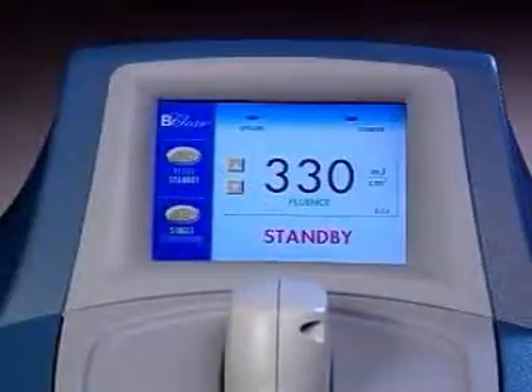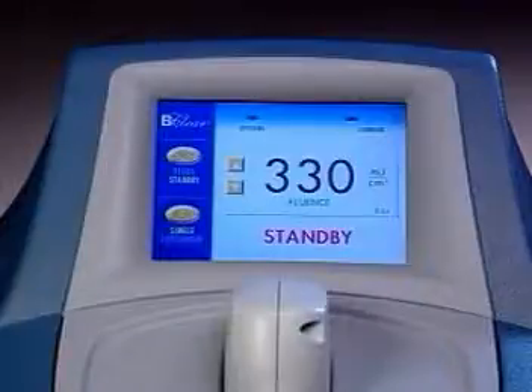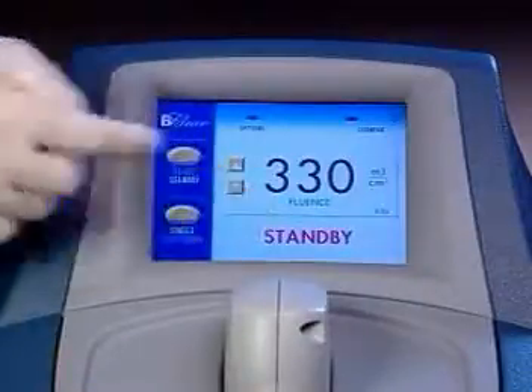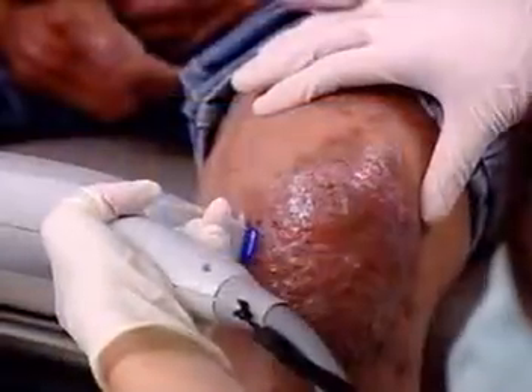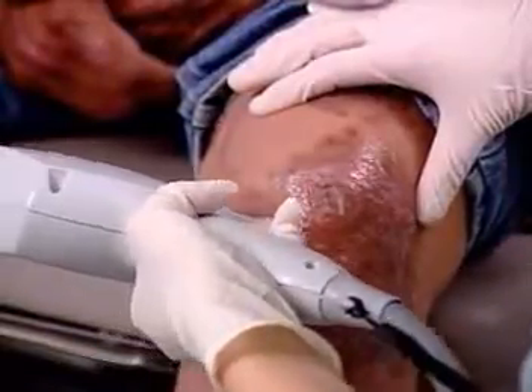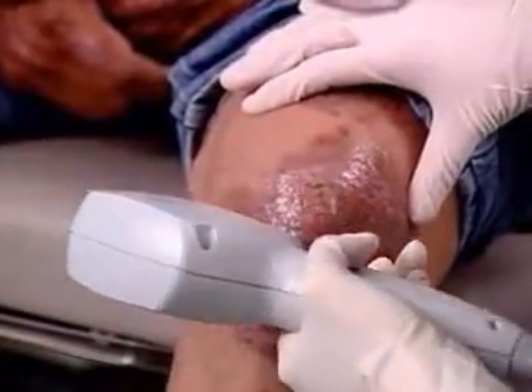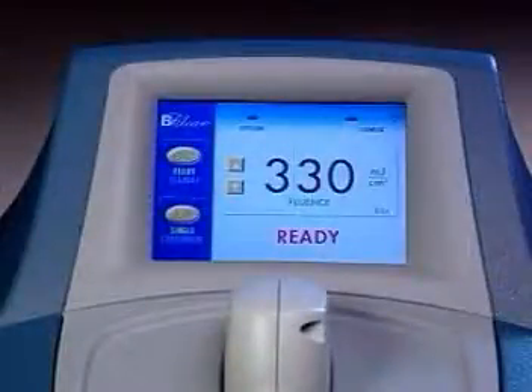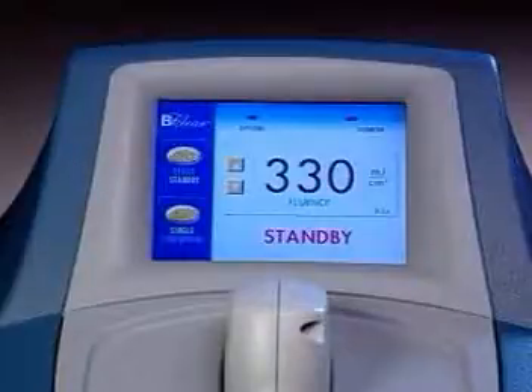In the Standby mode, the system is ready for use but has not been activated. When in the Ready mode, the system is ready and will emit light whenever the foot switch is pressed. Adjusting any parameter, or if the system is not used for approximately 3 minutes, will cause the system to automatically return to Standby mode. This feature prevents unintended emission of light.